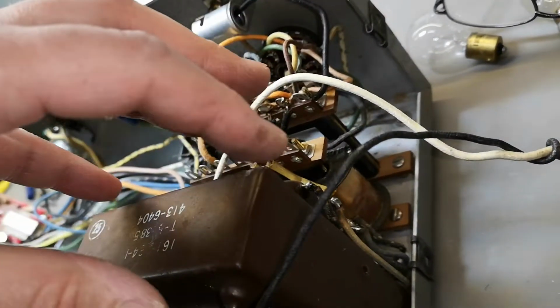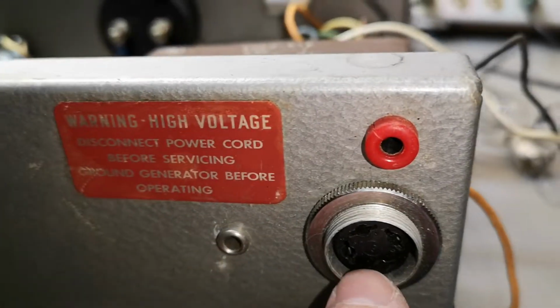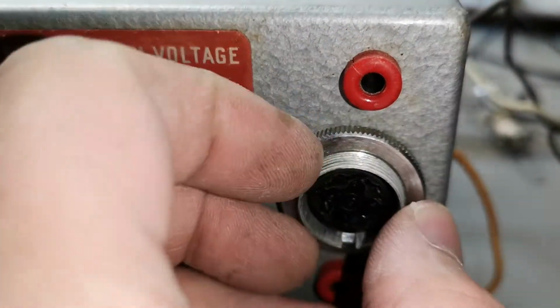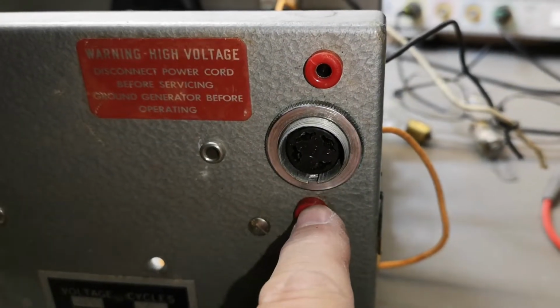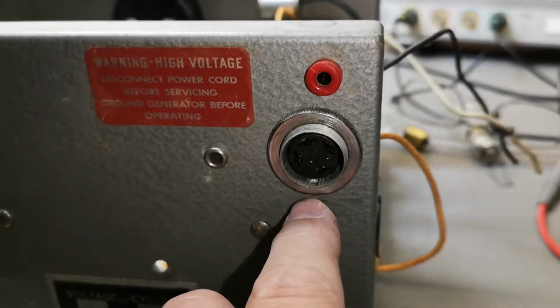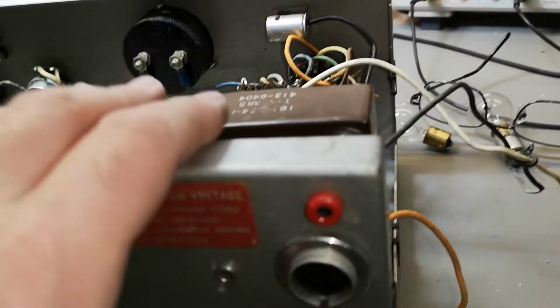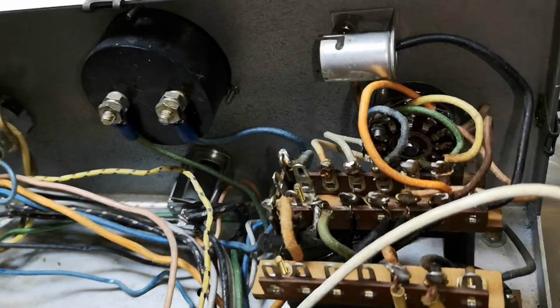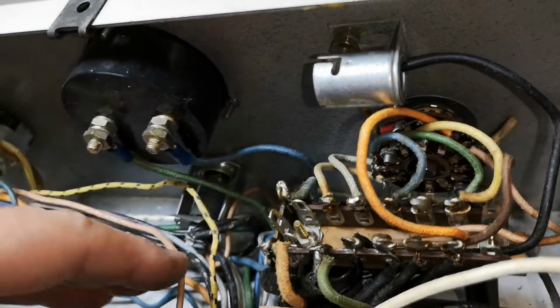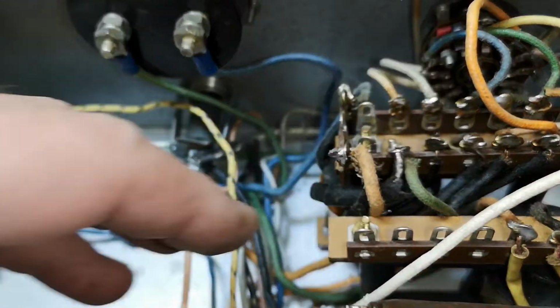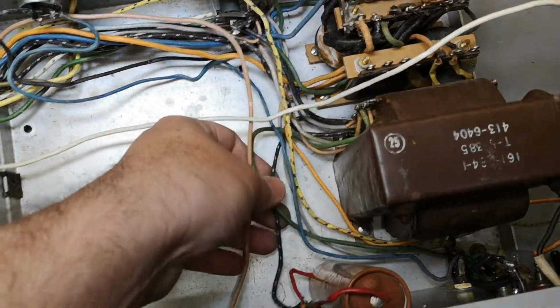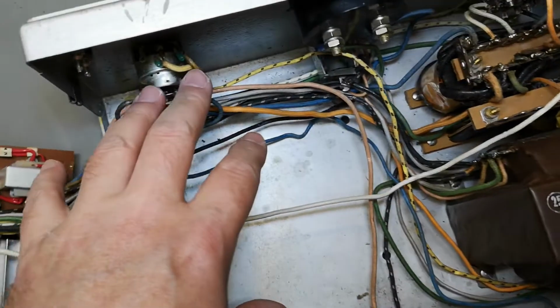It's not going to oscillate when the input drive or the input sense from the solenoid or the transducer is disconnected. I would probably call it a transducer. So when the transducer is disconnected, there is no oscillation, there is no feedback, and nothing is going to happen. So that means we cannot power this up. So yeah, I might as well pull it all the way apart. But it was fun to see the different routings and the wires and stuff.